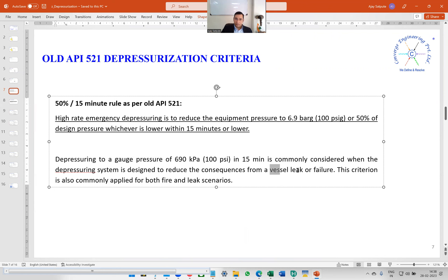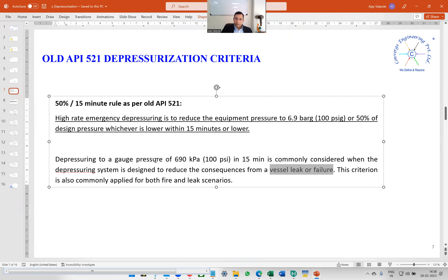Also, this statement is common to both old and new API: depressuring to a gauge pressure of 690 kPa in 15 minutes is commonly considered when the depressuring system is designed to reduce the consequences from a vessel leak or failure. So this criterion — 6.9 bar gauge final pressure within 15 minutes — is commonly applied for both fire and leak scenarios.